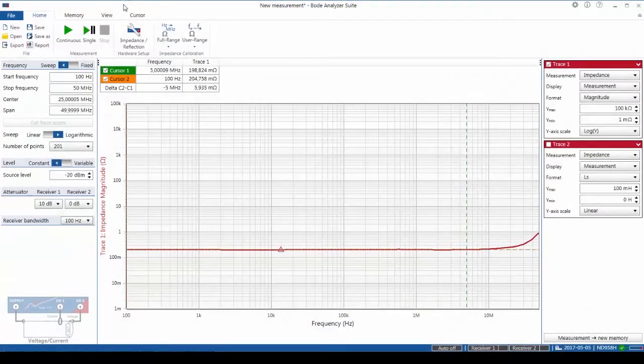With those set, we can now go and perform a calibration. Here I'm using the user calibration, which provides us with the best fidelity, particularly at high frequencies.